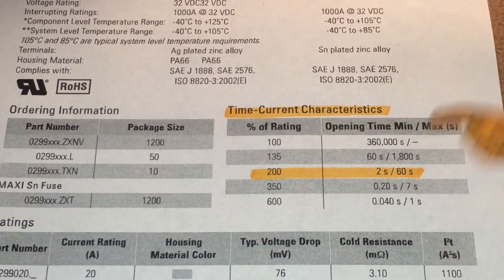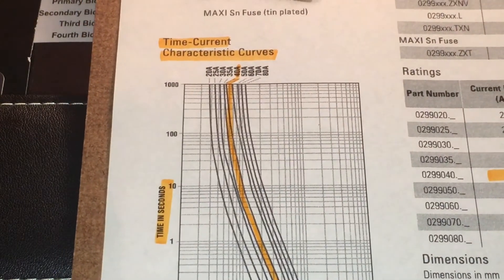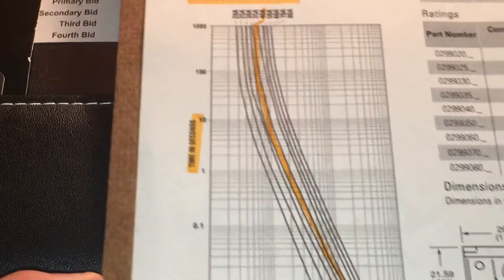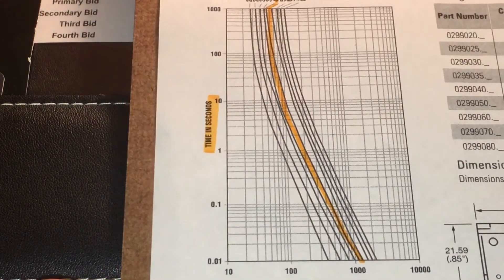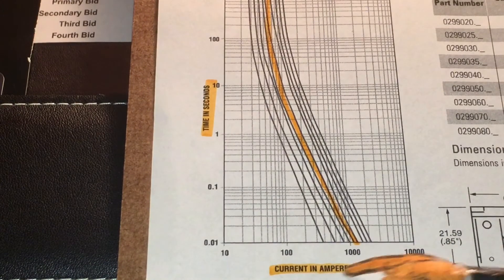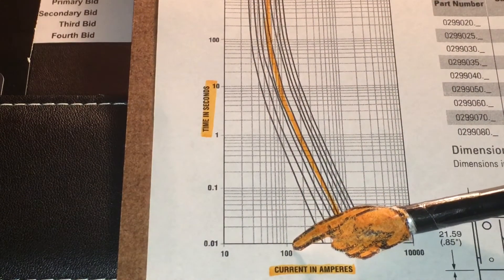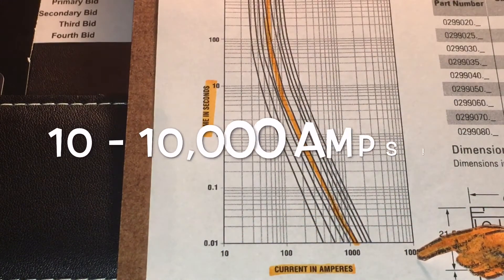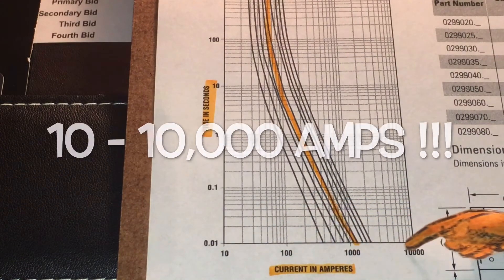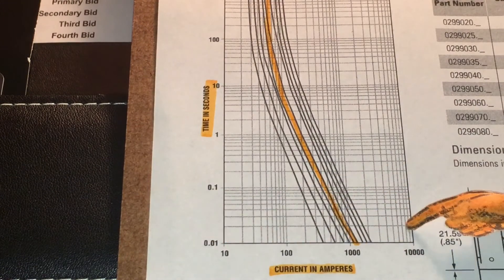People think that with a 40 amp fuse, as soon as it exceeds 40 amps it'll pop - that's not the case, and you can see it graphically in this graph. We have a time-current characteristic curve. Here's current in amperes and here's our time. Keep in mind this is ten to ten thousand amps on a logarithmic scale - not a linear scale.